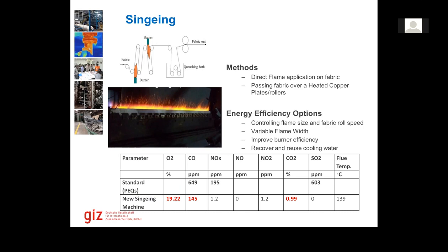Stack analysis - just put a stack analyzer in the exhaust chimney. The singeing machine has an exhaust chimney which throws out air, taken directly from the burner, with smoke going up and out of the factory. You do a stack analysis there, measuring the oxygen quantity and the flue gas temperature, which tells us if optimization can be done.